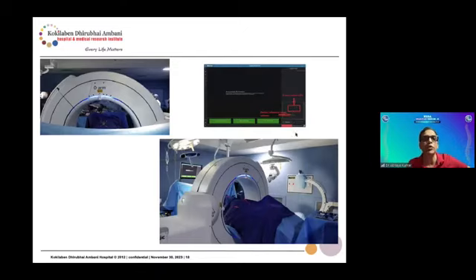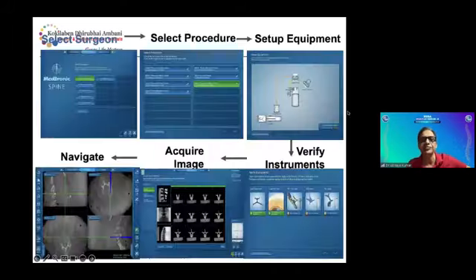One thing we need to know before you do the imaging, there are trackers on the O-arm itself, on the machine itself, which have to be reflected on the monitor. If by chance you miss this, whatever imaging you do will go to waste, and you will not be able to navigate. So before you take an imaging, you need to see that the reference arc tracker spheres and the O-arm tracker spheres are visible on the monitor.